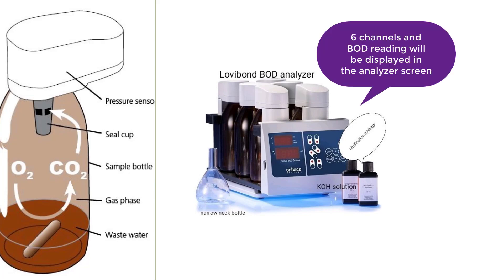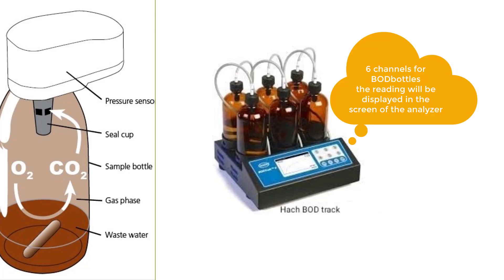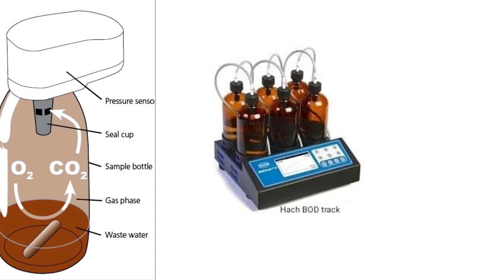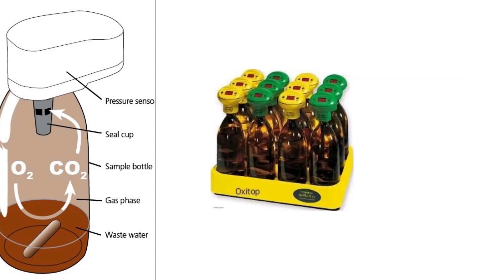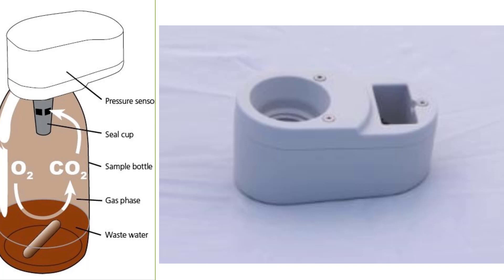I have selected a few BOD analyzers to share here. Starting with the Lovibond unit — it contains six channels and a display screen. The second one, from Hach company, also has around six channels and a display screen. The third one is from OxiTop company; it has around 12 channels and the BOD reading appears on the cover itself, which makes it a special one.